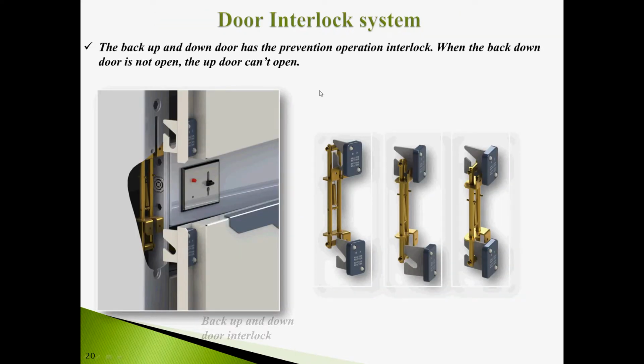Okay, here is how it goes. This is the back door. When you close the earthing switch, the back door will unlock. Then you have to press a button to release the second interlock part, so the back door can open. This is to make sure that all the electricity is powered off by placing the earthing switch. So this is the second comprehensive interlock protection for the maintenance people.